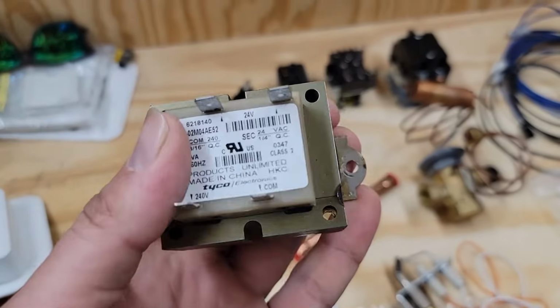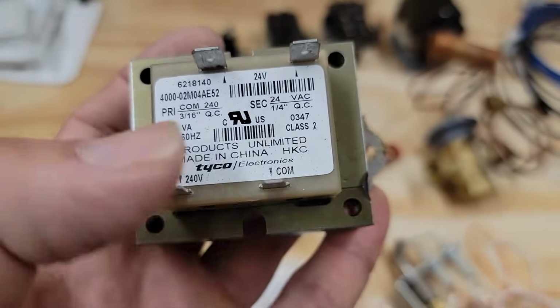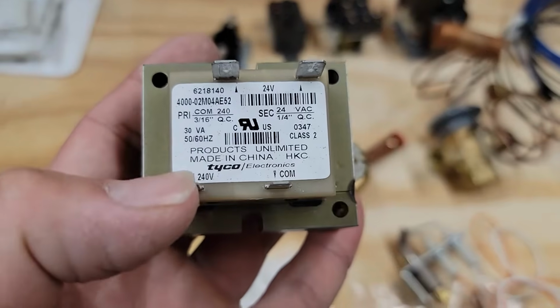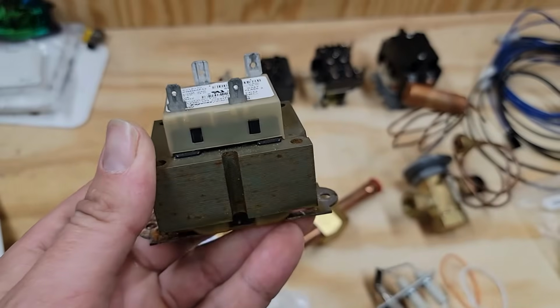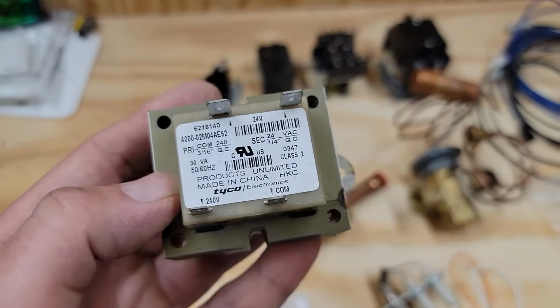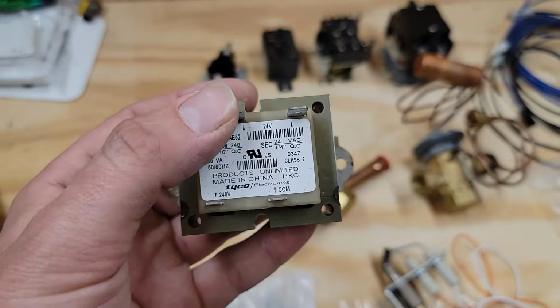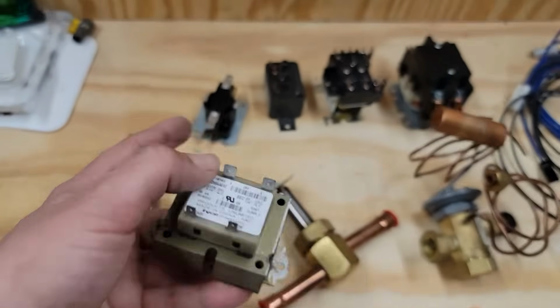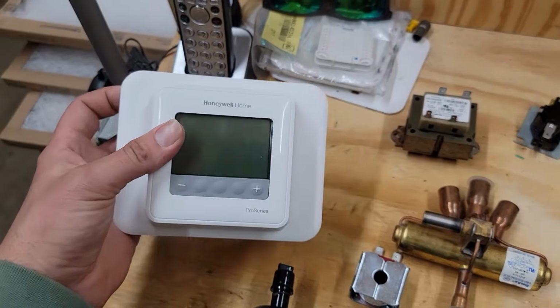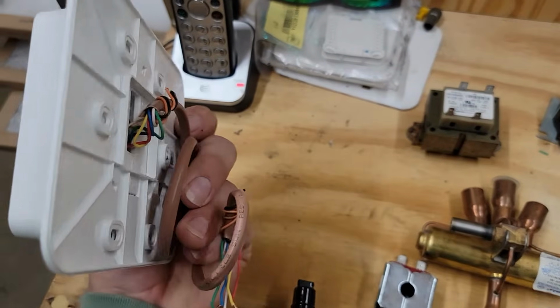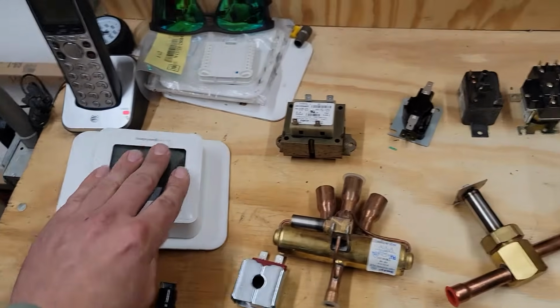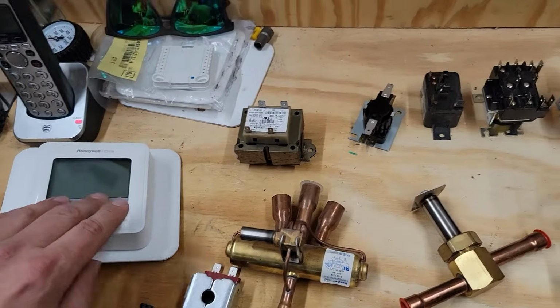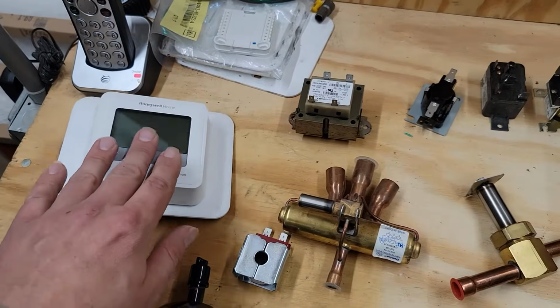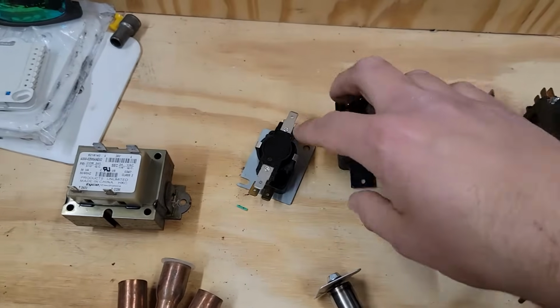This is a transformer, and you can see it says 240 volt and common, and this is where our line voltage would come in, and this is where our low voltage would go out. And this transformer basically steps down the voltage, from line voltage to control voltage, so we can control things like these relays or this thermostat, because this is a remote control. This is a control that works off control voltage, and it's used to operate the equipment, to either change from heat, cool to off, and that's what the thermostat does.